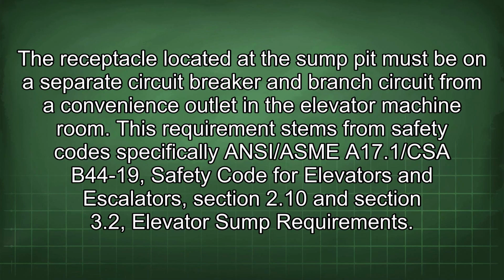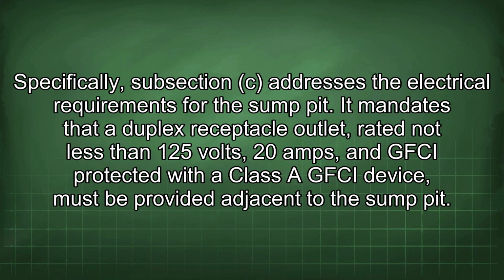The receptacle located at the sump pit must be on a separate circuit breaker and branch circuit from a convenience outlet in the elevator machine room. This requirement stems from safety codes, specifically ANSI/ASME A17.1/CSA B44-19, Safety Code for Elevators and Escalators, Section 2.10 and Section 3.2, Elevator Sump Requirements. Specifically, subsection C addresses the electrical requirements for the sump pit.